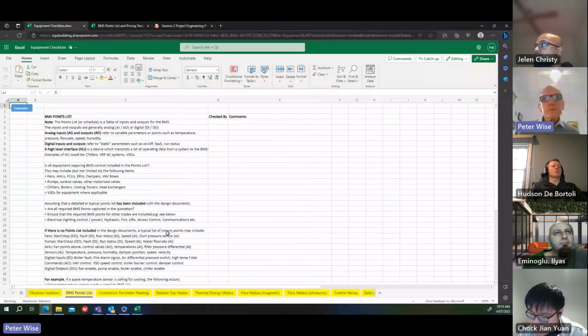A BMS system will include software graphics of the controlled systems, based on the approved points list and functional description. The graphics enable operators to monitor and change system operating parameters as required when the HVAC systems are in operation. The engineer works with the control subcontractor during development of the graphics to ensure they are correct. Progress review meetings with stakeholders may be required during this development process.